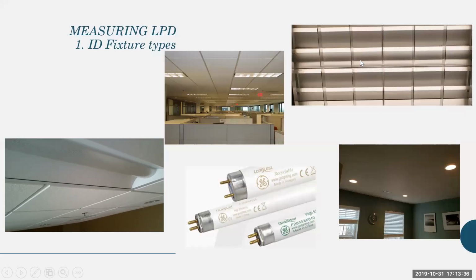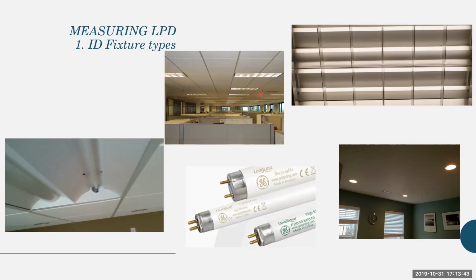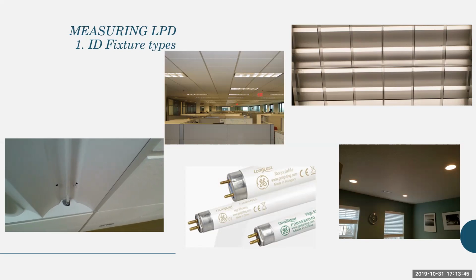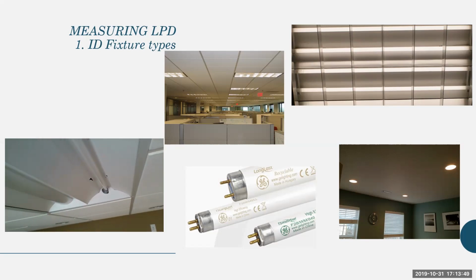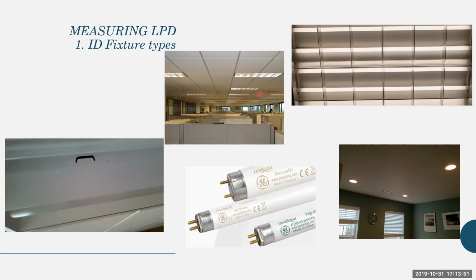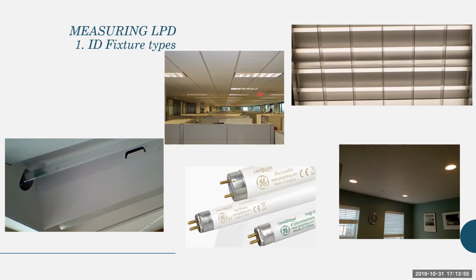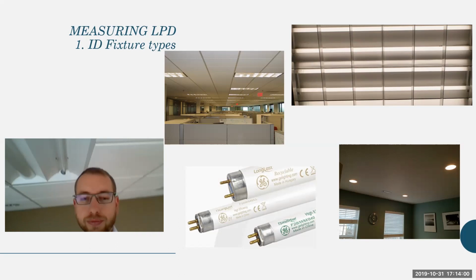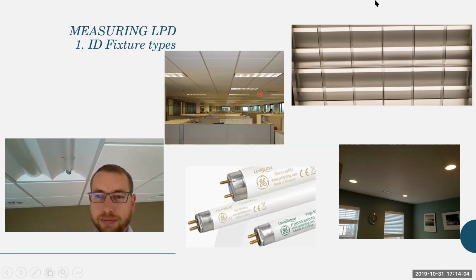All right, so here is an up-close view of that fluorescent light fixture we were looking at earlier. I took the liberty of popping the cover off the other side, and you can see there that it is a very skinny bulb. It is a T5 bulb, and if you look on the very end, you can actually see the wattage. This one is a 28 watt bulb. All right, now that you've seen that, let me pause again.